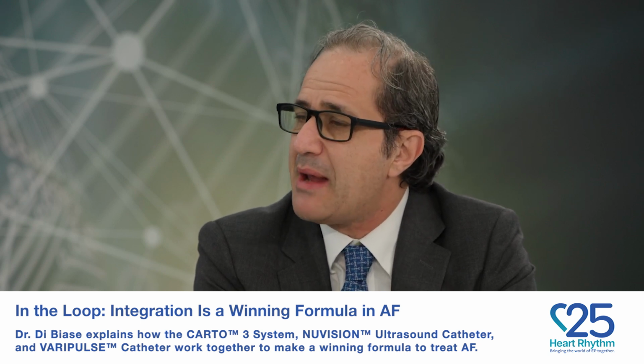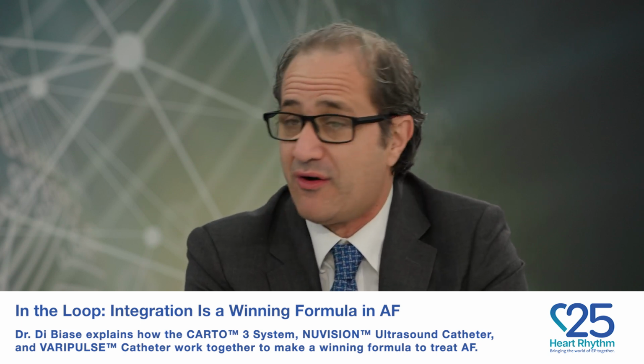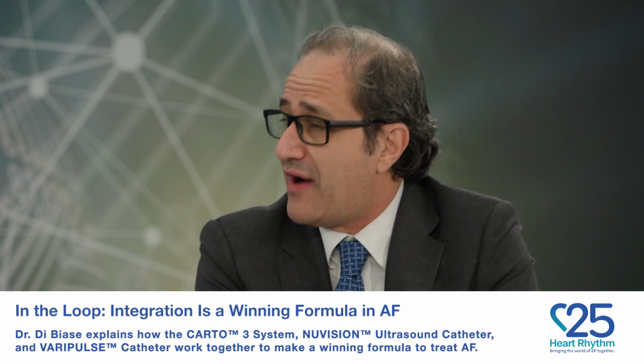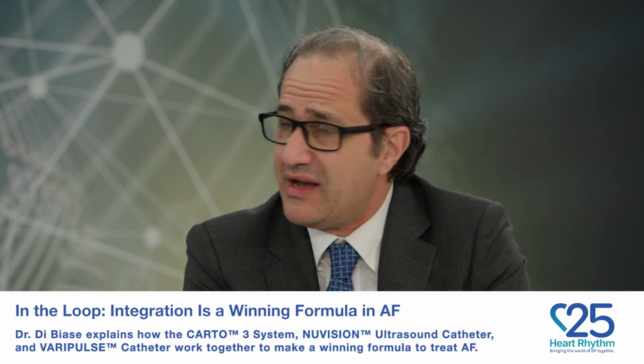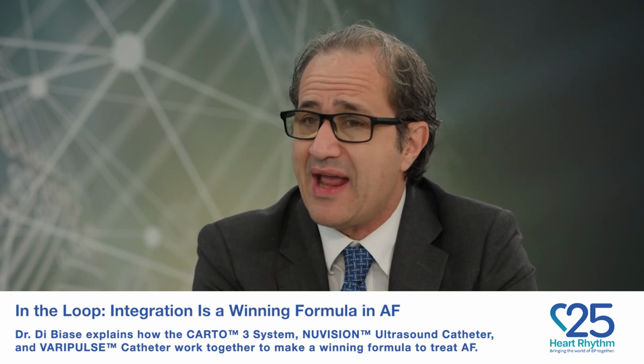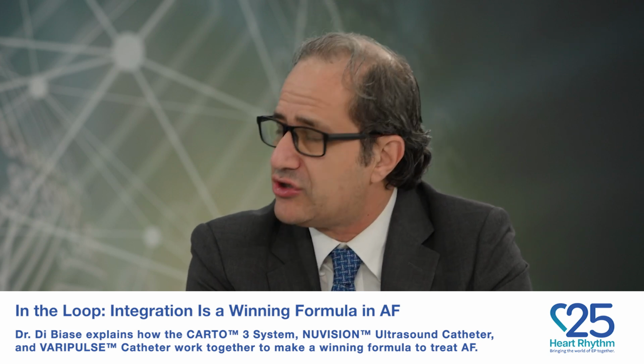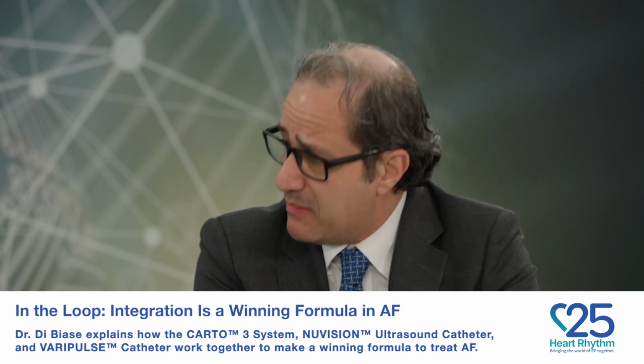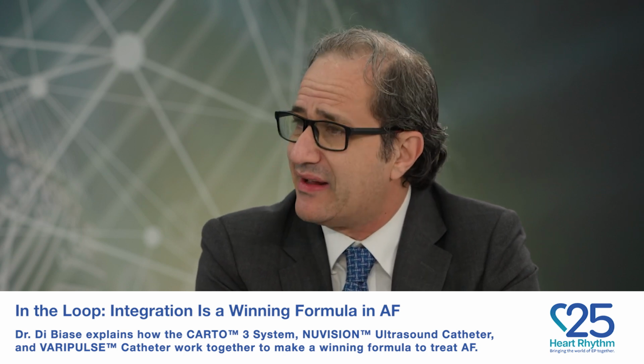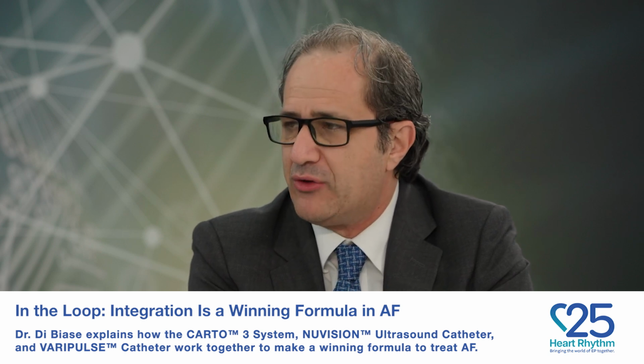Second advantage is the same catheter can map and ablate, remap and reablate or verify isolation. And you can verify isolation through pacing maneuver. It's a circular catheter, so you can put this in the vein and just go around the electrodes. You can do pacing, you can do voltage. One possible limitation about the remapping with this catheter is that the electrode size is big, it's not as small as an octa-array or a penta-array or any other multimodality mapping. So you really need to discriminate well between far field and real reconnection.